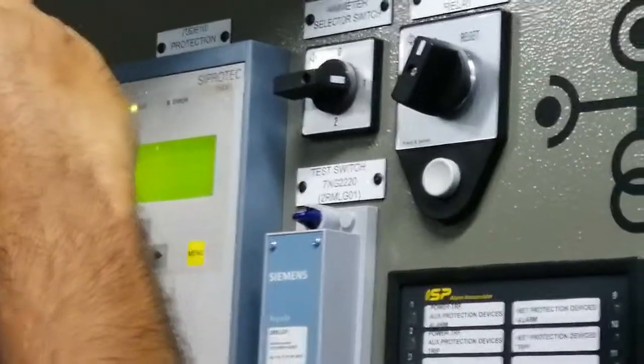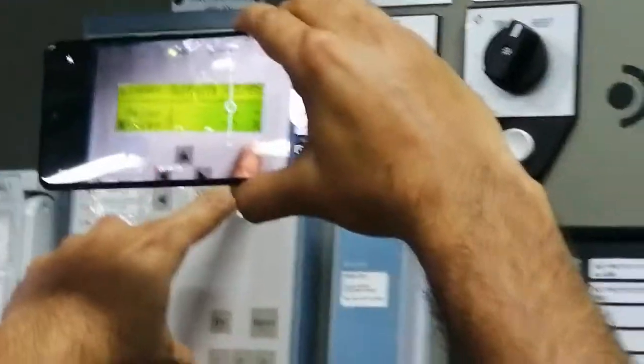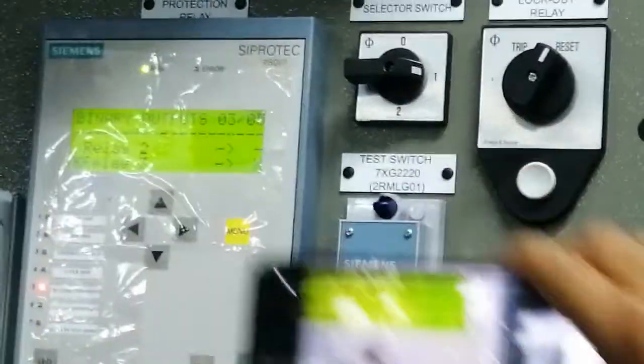So as you can see, this is binary output, and binary output number 3 is high now. For the ABB relay, this binary output of the Siprotec relay is coming on binary input 1 of the X120 card of the ABB relay. So this is the ABB relay side. We'll show you the input. That will also be high now. So that is true now.